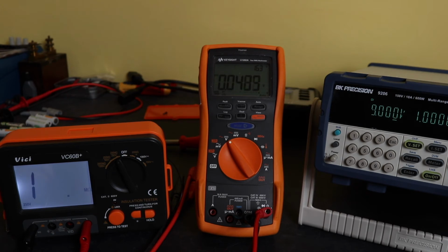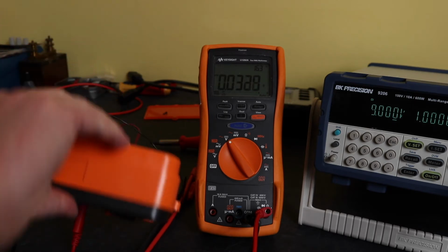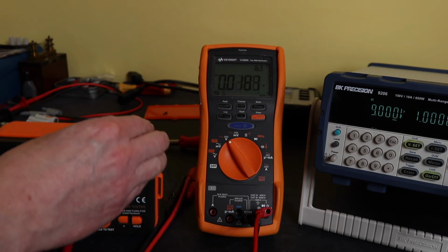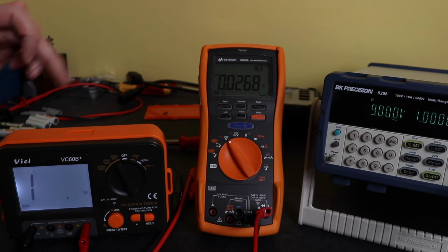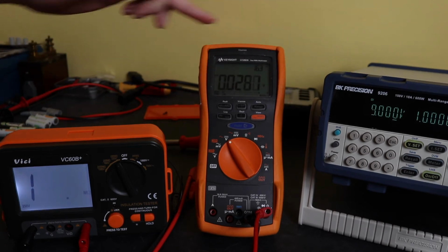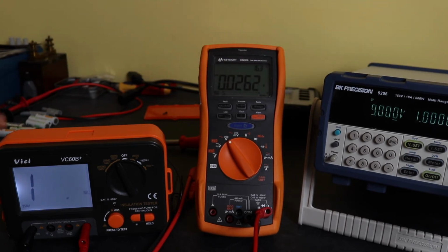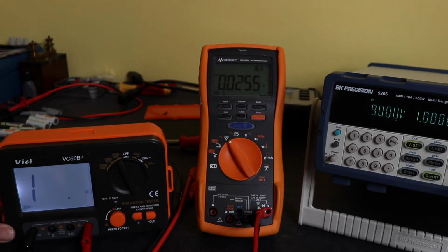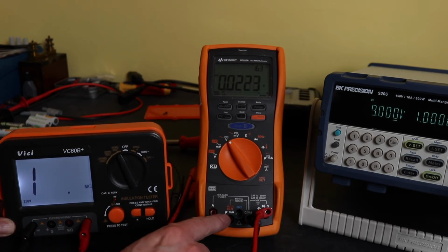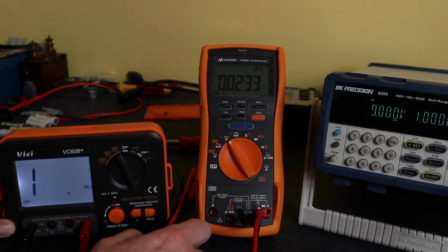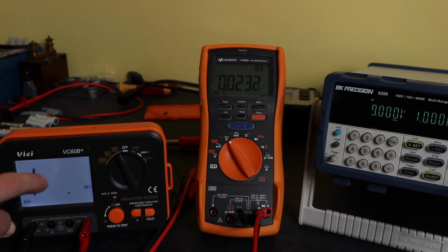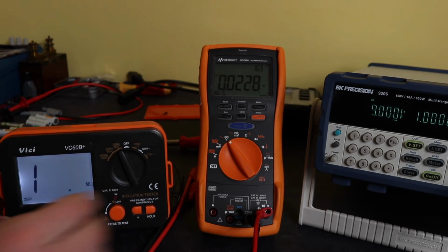Okay, so I just want to go through one of the issues I've found on this Vici unit. At the moment I have removed the battery pack, and I've put in these two dummy cells and these two adapters here, and I'm feeding the battery pack via this DC power supply over here. It's set to 9 volts to match the 6 AA batteries that would normally be in here. I've wired the output of the instrument onto a DC voltmeter here so I can measure the output voltage of the insulation test function, which at the moment is on 250 volts.